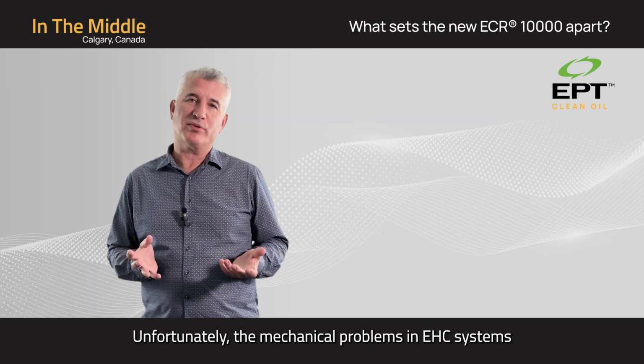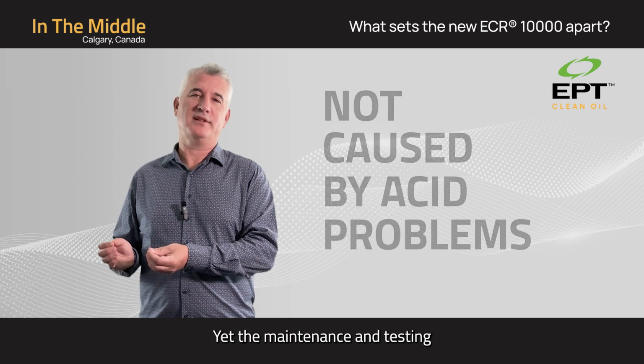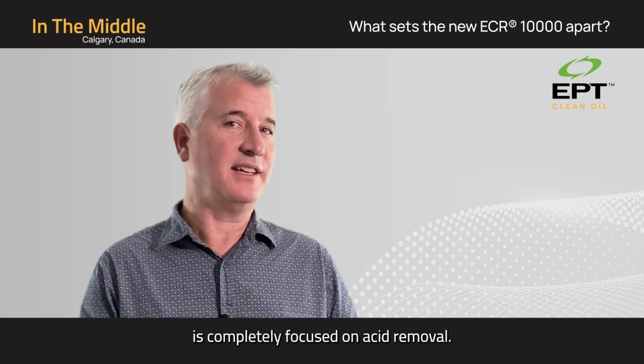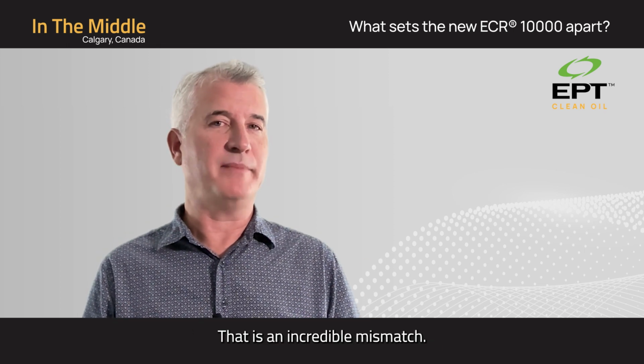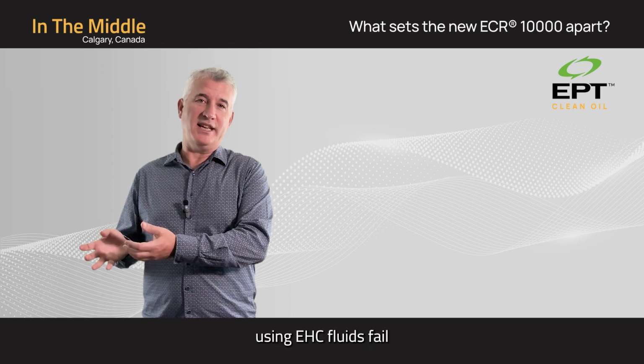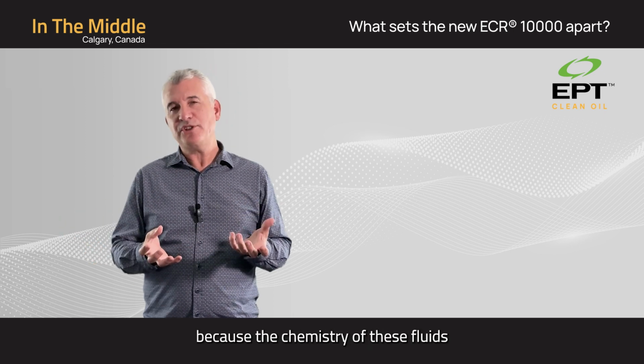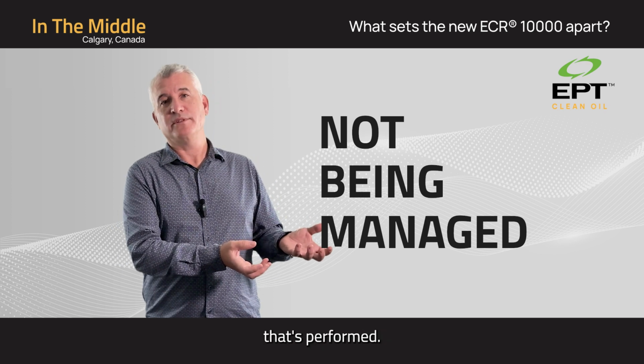Unfortunately, the mechanical problems in EHC systems are not caused by acid problems. Yet the maintenance and testing is completely focused on acid removal. That is an incredible mismatch. EHC fluids fail, and mechanical systems using EHC fluids fail because the chemistry of these fluids is not being managed with the existing maintenance that's performed.